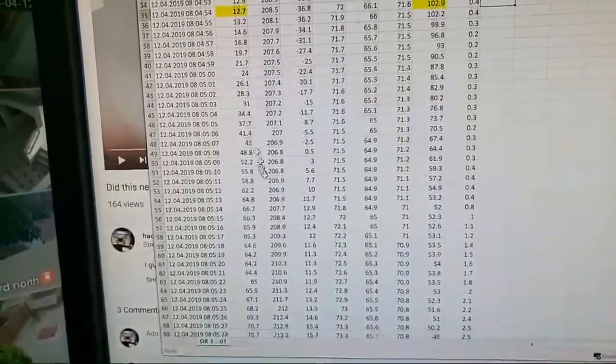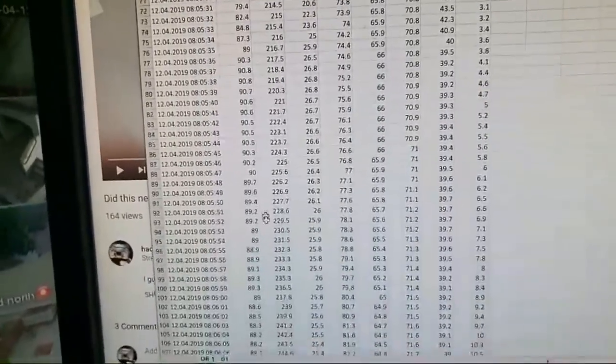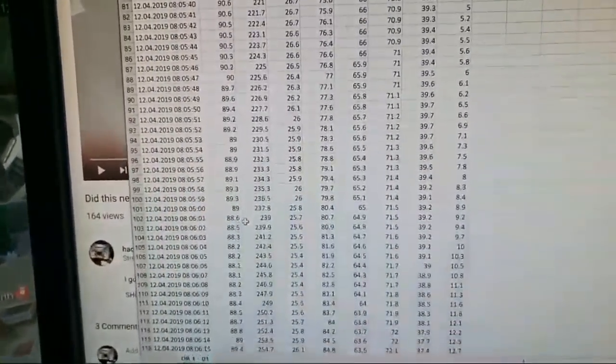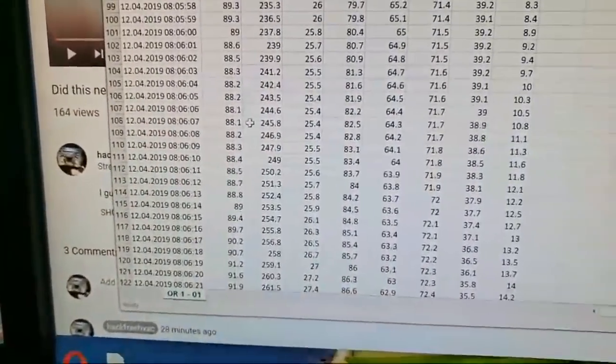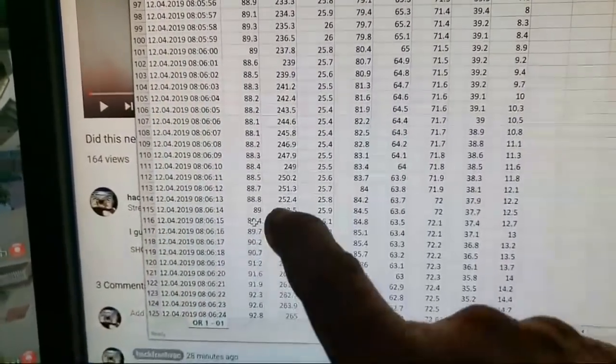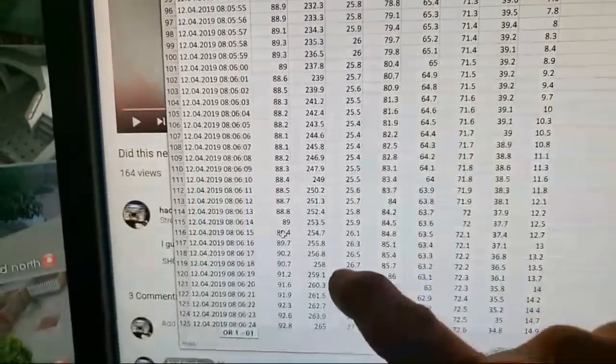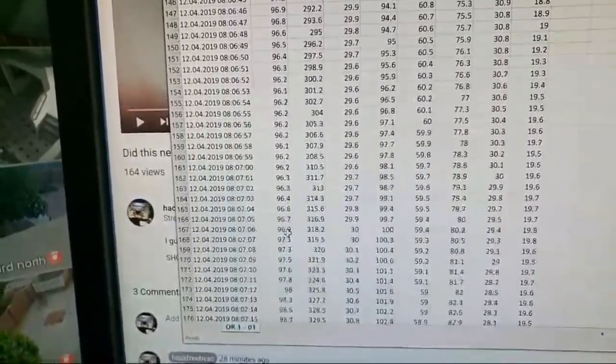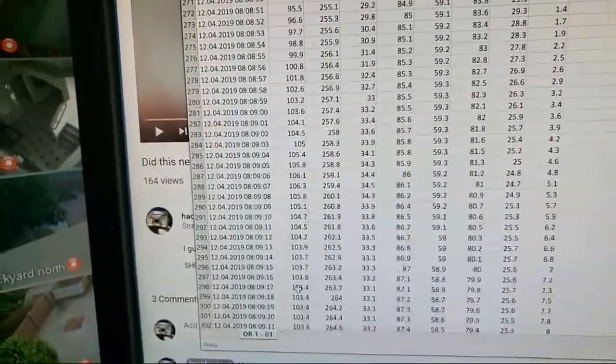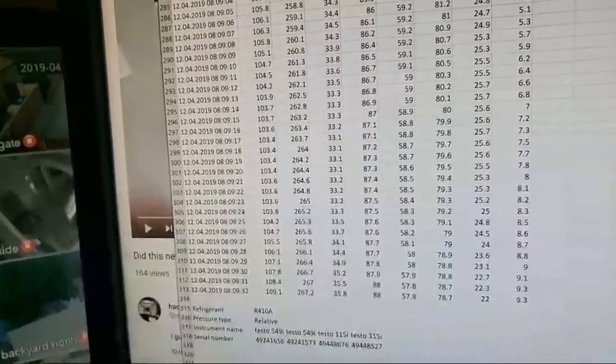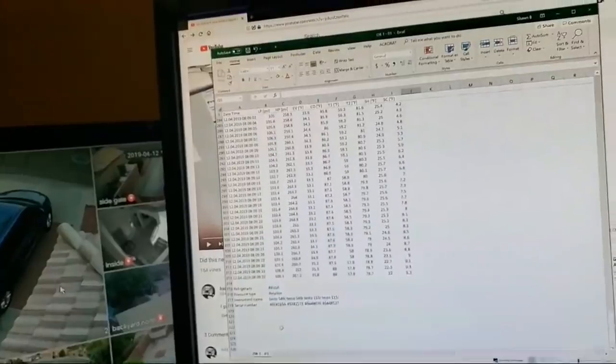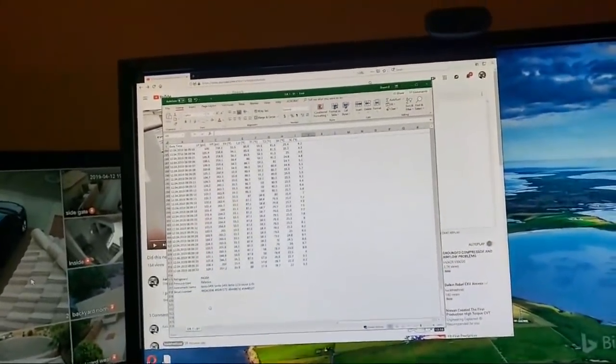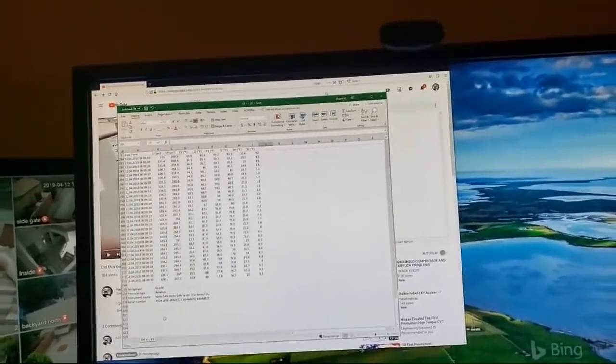The alarm actually was put in like months ago, but they're still not using these operating rooms. And somebody just happened to go in there the other day and noticed that it was not cold like it should be in that room. So that's what generated this service call. A bunch of things kind of threw me off on it. So basically, I cleared the alarm and ran it.